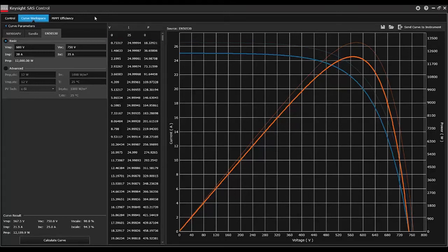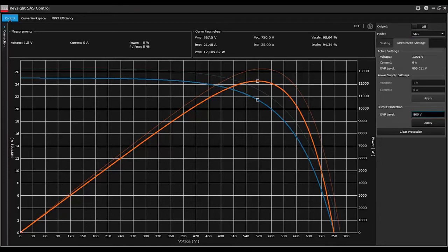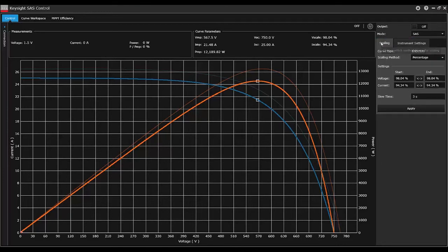From here, we can go to the Control tab in the top left, where we will see our new SAS curve. The Control tab shows different measurements and parameters of the DC power supply and also allows for controlling the instrument. On the right, we have two different tabs for controlling the instrument via scaling and instrument settings. It also allows us to change the output state and the operation mode. Right now, we'll keep it in SAS mode.